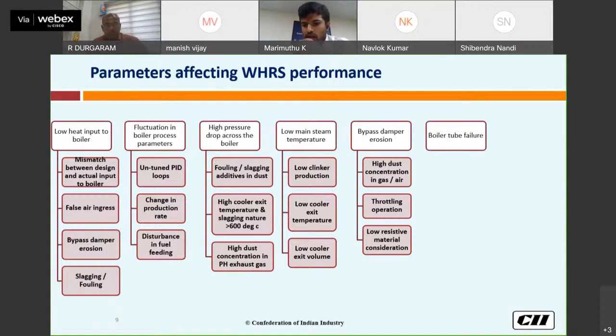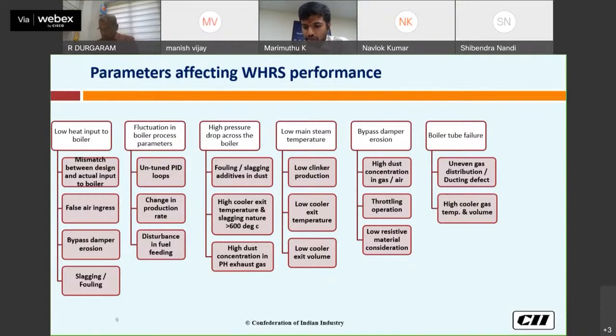Then another one, boiler tube failure. Boiler tube failure mainly occurs due to uneven gas distribution and ducting defects. If the gas distribution is not good, then in some areas we will get more gas, which causes more velocity, so definitely the erosion will take place. So this is one reason we observe.